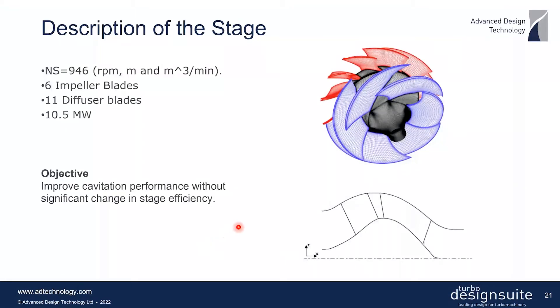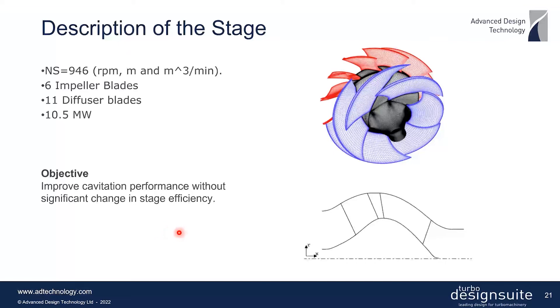This was a fairly high specific speed mixed flow stage with a specific speed of 946 in terms of rpm, meters, and cubic meters per minute. There were six impeller blades and 11 diffuser blades. The baseline stage already had quite high efficiency, so the purpose of this redesign was to improve cavitation performance without any significant change in efficiency, since what's good for cavitation is not always good for efficiency.